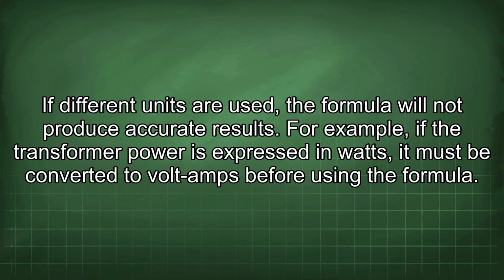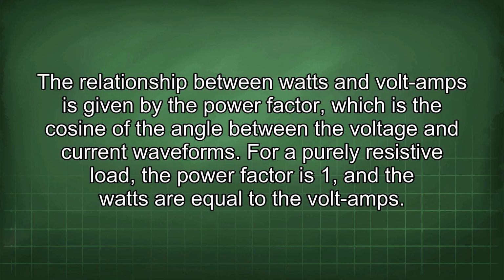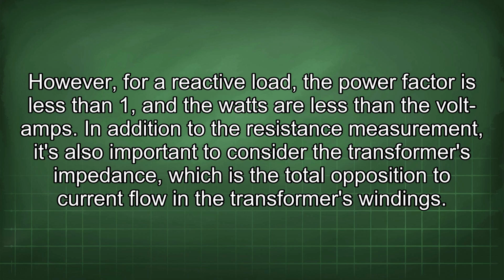For example, if the transformer power is expressed in watts, it must be converted to volt amps before using the formula. The relationship between watts and volt amps is given by the power factor, which is the cosine of the angle between the voltage and current waveforms. For a purely resistive load, the power factor is 1 and the watts are equal to the volt amps. However, for a reactive load, the power factor is less than 1 and the watts are less than the volt amps.